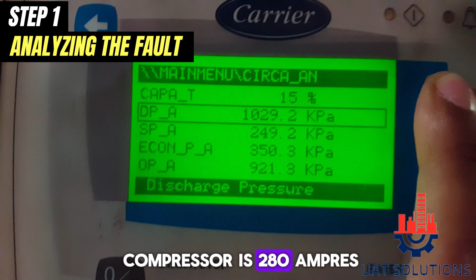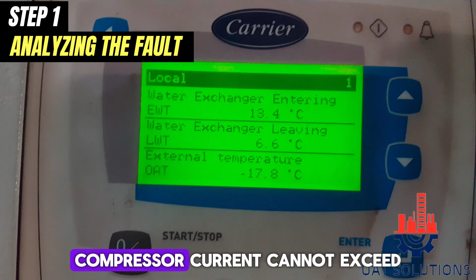As shown in the display, current consumed by the compressor is 280 amperes, while compressor capacity is shown at 15%, which is abnormal. At 15%, compressor current cannot exceed 110 amperes.